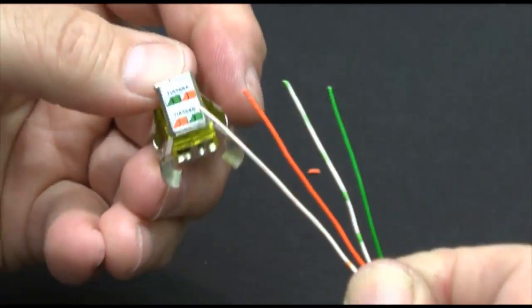Open the small door and start to insert the conductors by color code, inserting the longest conductor, the orange stripe, into the first hole to the left, followed by the second conductor, then the third and fourth sequentially through the color coded holes.